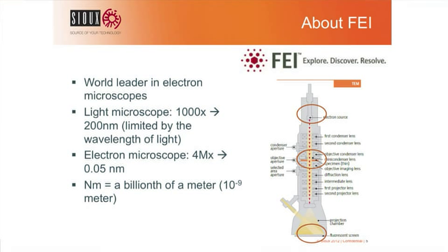That is the object you are interested in and that you want to magnify. A lot of electrons will travel through the specimen, but several will also bounce back, hitting other material. The electrons traveling through the specimen will hit a so-called fluorescent screen, where the image is in fact being magnified because we have several different electromagnetic lenses in the system. This fluorescent screen can in practice also be a CCD camera, and with a CCD camera you can get the images on a computer screen. In this way we can get magnifications of millions of times.